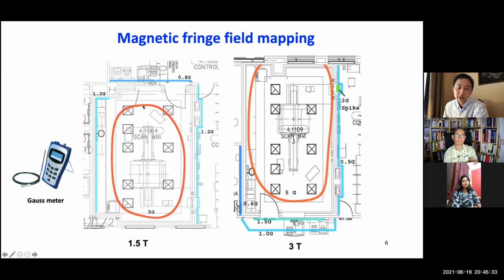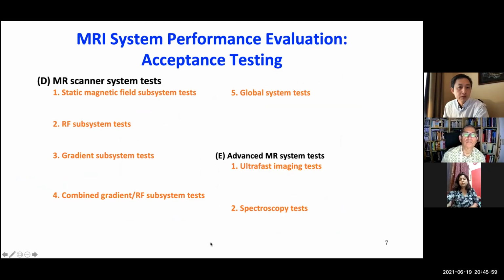measure at different locations. Here the red curve shows the 5 Gauss line of a 1.5T scanner, and on the right-hand side is the 5 Gauss line of a 3T scanner. Typically, we will map the complete 5 Gauss line plus the location at the console, the working area. So those are acceptance testing. We don't do those annually, okay?